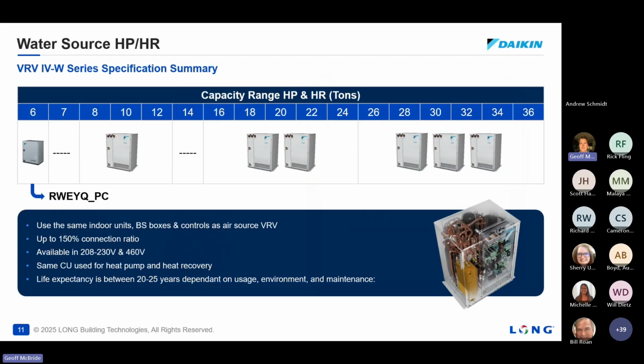This is our water source lineup. It runs from 6-ton to 34-ton for Daikin. We don't see a lot of water source heat pumps, which is surprising to me, because of our degree day disparity in Denver. We have very cold days and very hot days, and water source would be a very good product. I think it's just because the air-cooled systems are rated down to -22, and you're able to eliminate a lot of the water side products like boilers, pumps, and cooling towers. And I think everybody's looking to get the best bang for the buck upfront cost. So I just wanted to let you know that we still have these. We see about 5% of our projects in Denver go water cooled. I think it's a great product. It's just going to be a little bit more expensive, a la water source heat pumps.